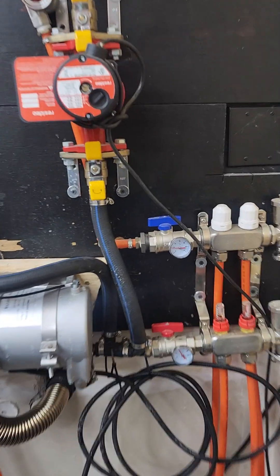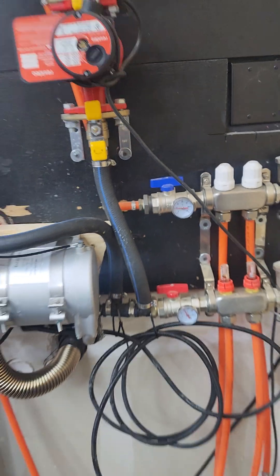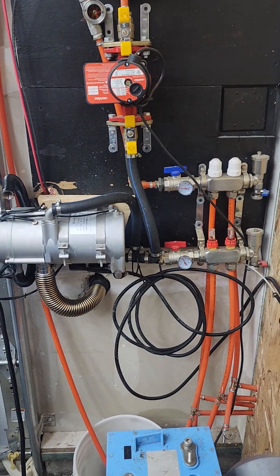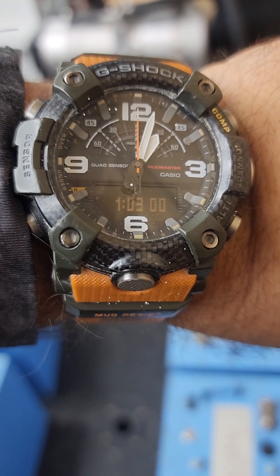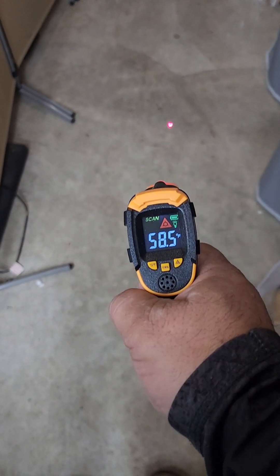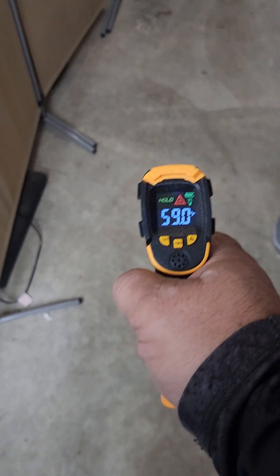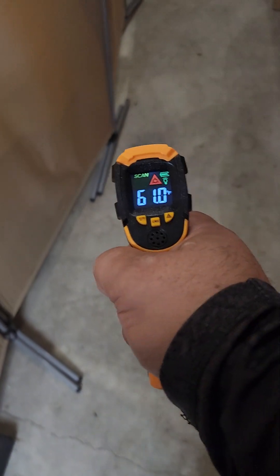The temperature coming back is about 20 degrees Celsius, and it has been on for four hours. I put it on at 9 a.m., and now it's 1. The temperature of the floor was 55 degrees at 9 a.m. Right there it's 59, right there it's 58.